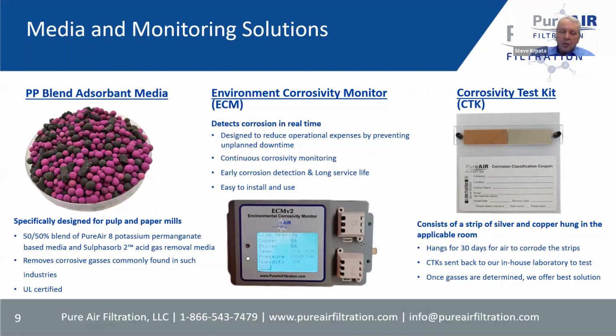The monitor in the center, the ECM, ours right now, we have an ECM V2, which is what's displayed there. Basically in real time, it tests and reports on 5 different factors that are present in whatever room it's placed in. So it will show you what the corrosion factor is and give it a grade, G1, G2, G3, GX. For copper, the top sensor there is a copper sensor, and the bottom sensor is a silver sensor. So that's consistent with the ISA standards.